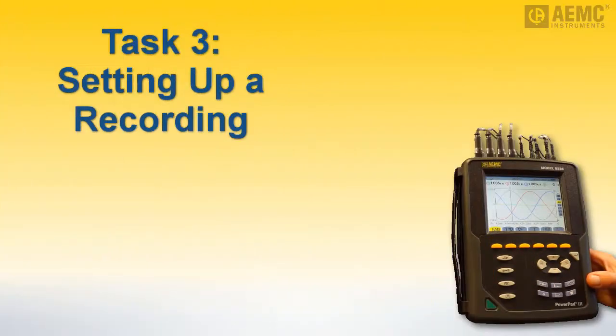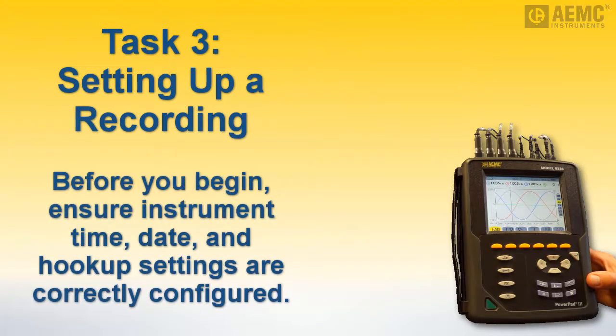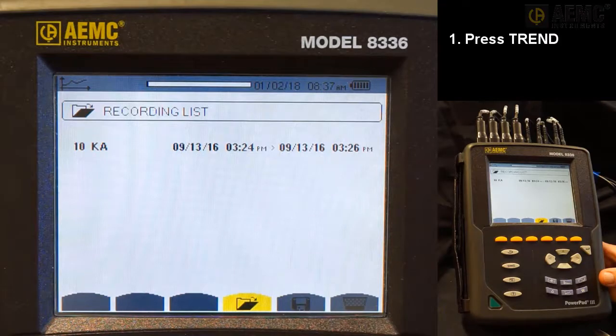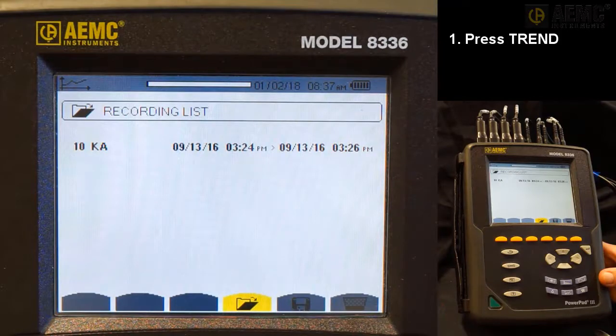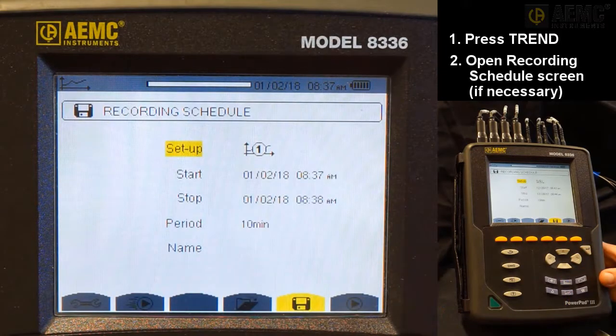Before setting up a recording session on the Model 8336, ensure the instrument time and date are correct. Also ensure the appropriate hookup setting is selected. These topics are covered earlier in this video. Press the Trend Mode button. If there are no recordings stored in the instrument, the Recording Schedule screen appears. If there are stored recordings, as is the case here, the Recording List screen is displayed. In this situation, press the yellow function button under the disk icon to display the Recording Schedule screen.